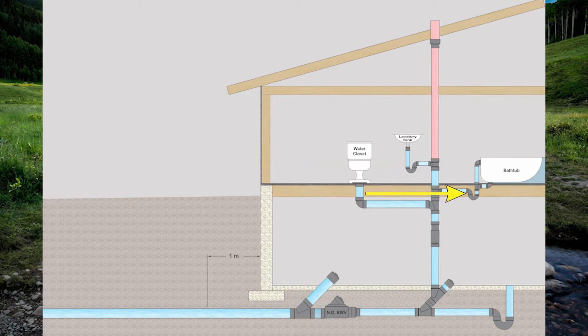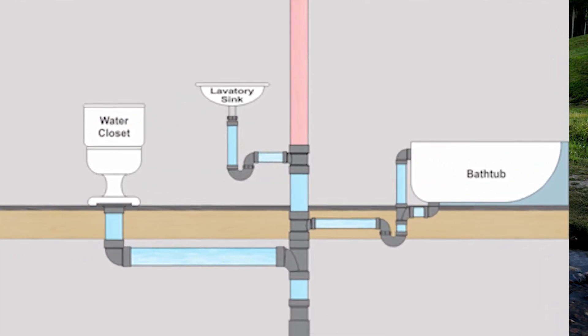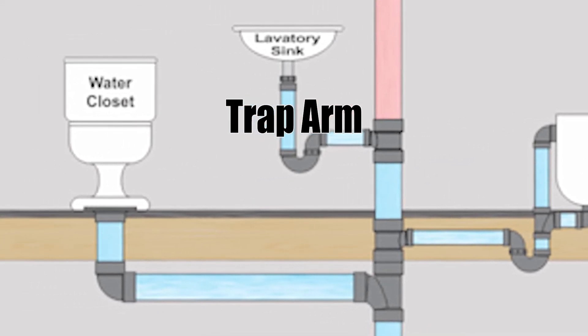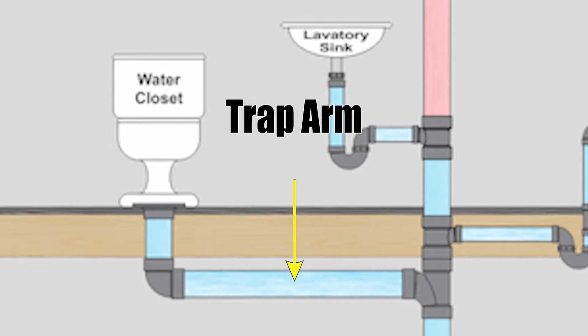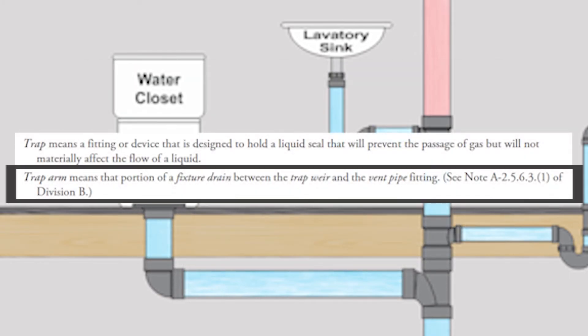You'll notice a U-bend in the pipe below the lavatory sink, the bathtub, and the floor drain in the basement — that is called a P-trap. That's an area where water sits in the pipe and basically plugs it off so sewer gas can't make it back into the house. If we look at the lavatory sink and bathtub, there's a horizontal pipe connecting the soil or waste stack to the trap — that is called a trap arm. You'll also notice a pipe extending from the bottom of the water closet — a fancy name for a toilet — heading over to the soil or waste stack. That is also a trap arm, but you don't see a P-trap there because the water closet has its own built-in P-trap, which is why you can always see water inside the bowl.